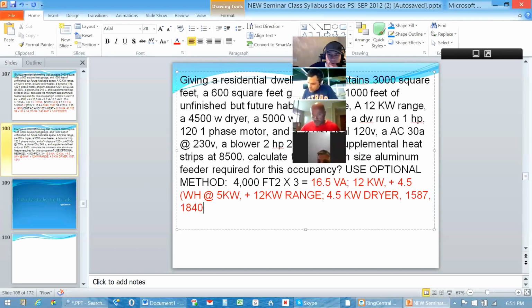1840, they're not necessarily in that order. And then 2760, that's what those three motors were in the standard method. And I'm going to take those at 100%. I'm not taking any increase for the biggest motor. So that's the last of the major differences there between the standard method and the optional method. All right, I'm going to add all of that together, but I'm not worried about the air conditioner heating.